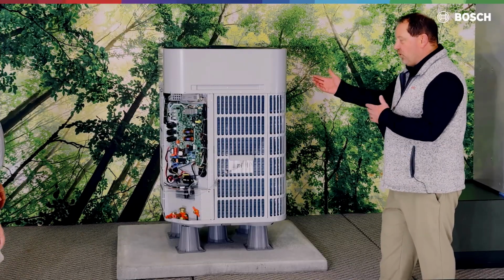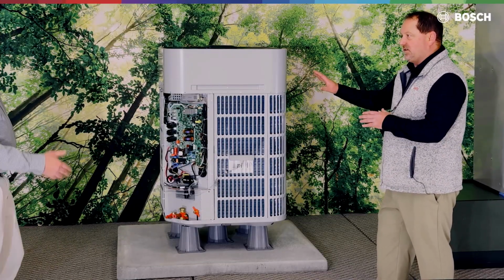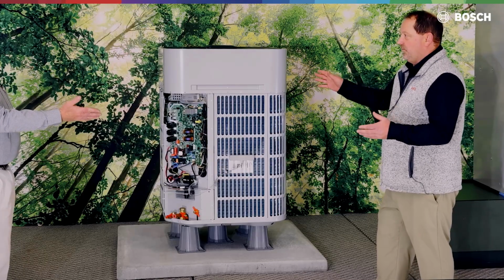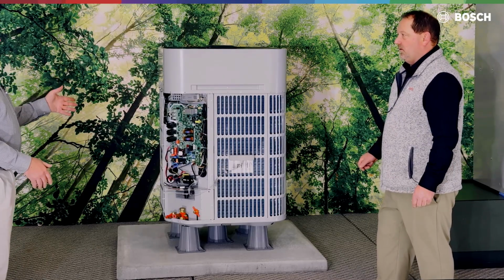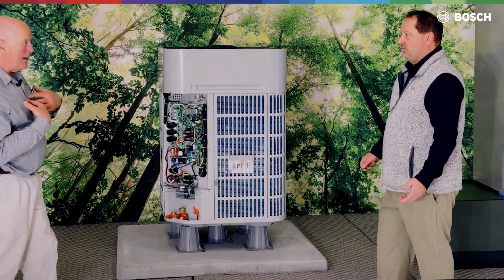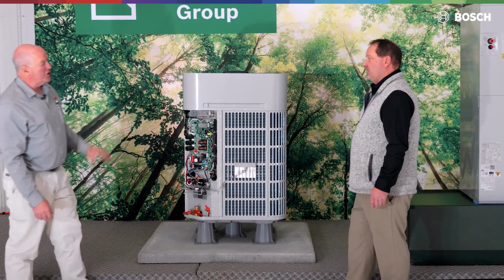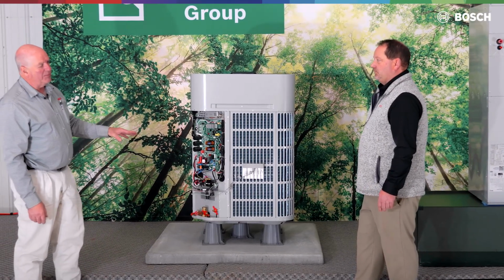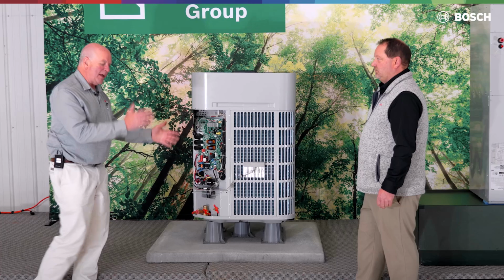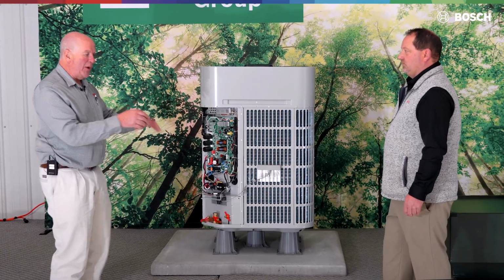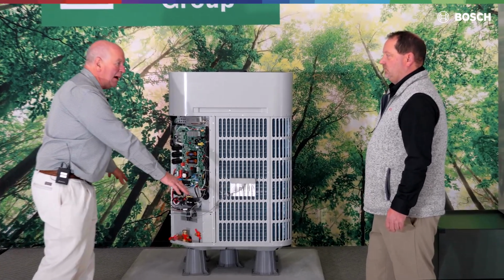So now we got line voltage connected to this thing. We did talk a little bit of safety on that. If we do line voltage, we're probably going to suggest to you having a disconnect out here. And we like a surge suppressor. That's my opinion, not that of Bosch. But a surge suppressor that's going to monitor that system. And we want something that's going to have a contactor, so if there's a problem with the voltage, this board goes completely dark.